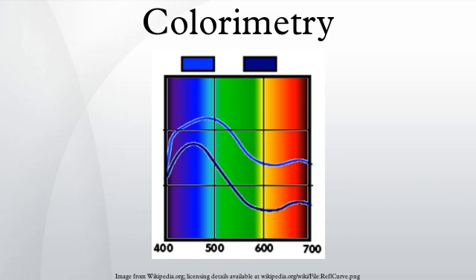Spectroradiometer, spectrophotometer, spectrocolorimeter: The absolute spectral power distribution of a light source can be measured with a spectroradiometer, which works by optically collecting the light, then passing it through a monochromator before reading it in narrow bands of wavelength. Reflected color can be measured using a spectrophotometer, which takes measurements in the visible region of a given color sample. If the custom of taking readings at 10 nanometer increments is followed, the visible light range of 400-700 nanometers will yield 31 readings.